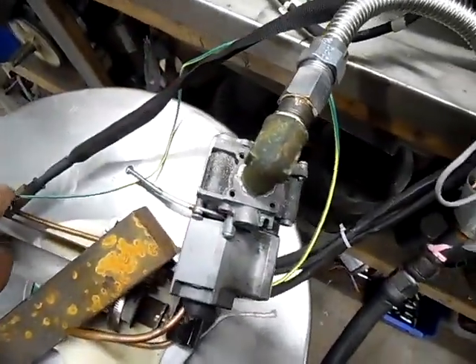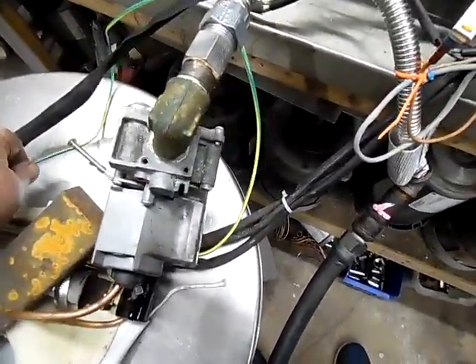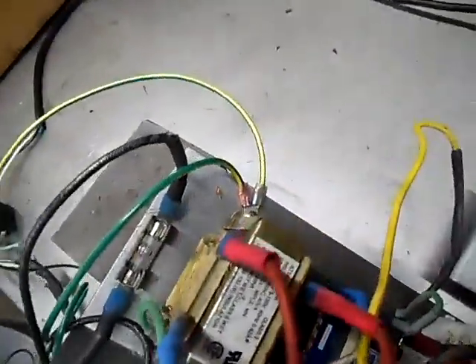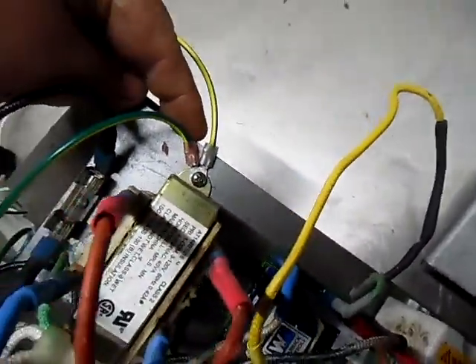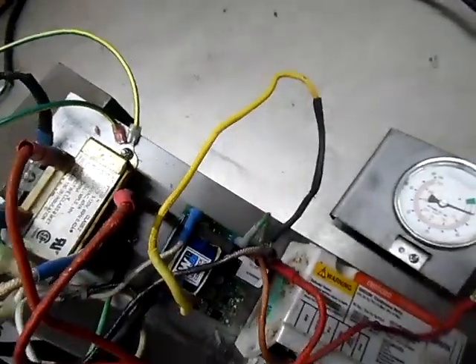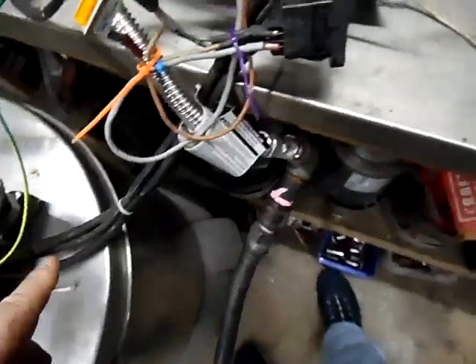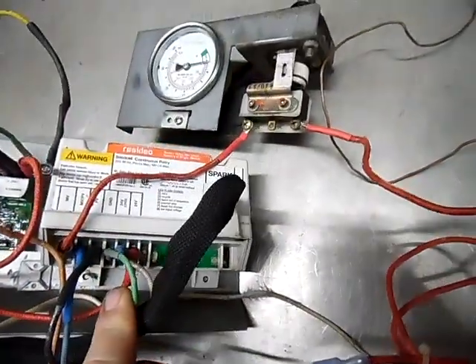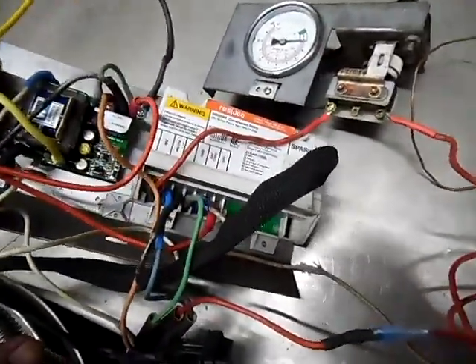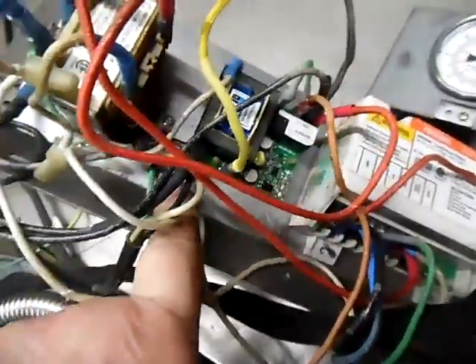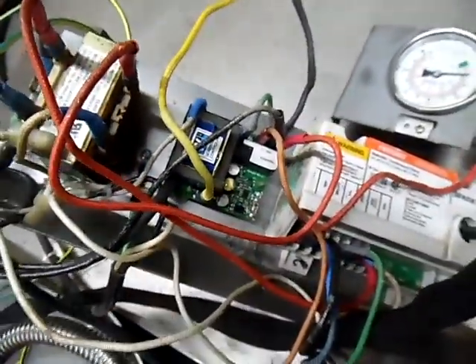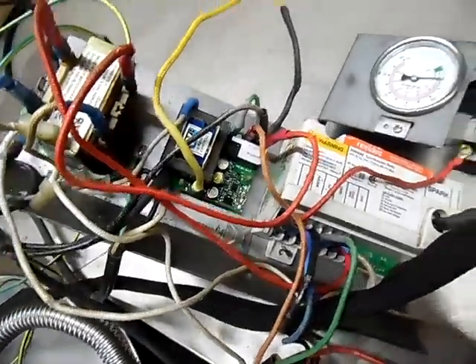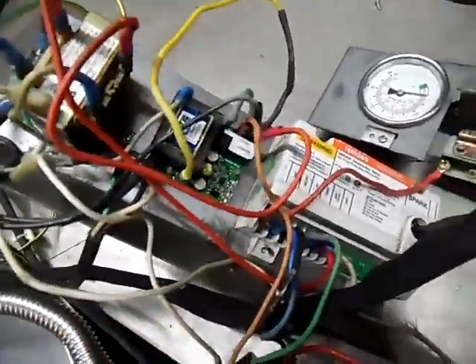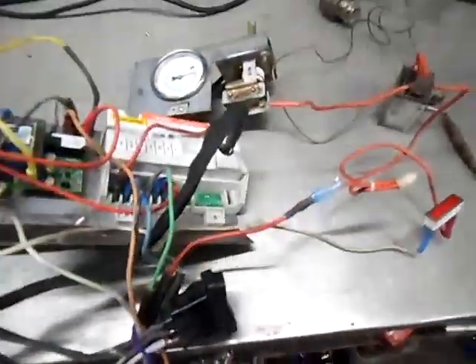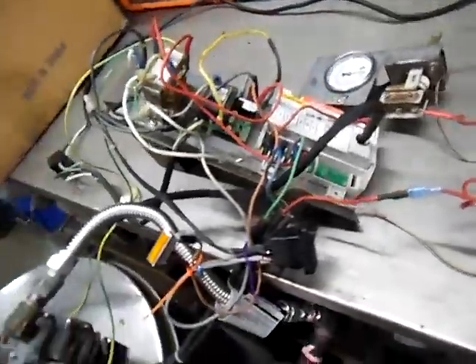So we found it better to run a ground wire all the way back, and this one will be heat shielded when we're done. And then we run it to the steel plate where everything's bolted, and you've got another ground wire here that runs back to the gas valve. The gas valve itself has a ground wire that goes to your box. So everything is grounded. Your transformer is grounded to the plate, and this metal that it's bolted to is also grounded to the rest of the machine. But what that does is give you a much more solid ground for the box to read.